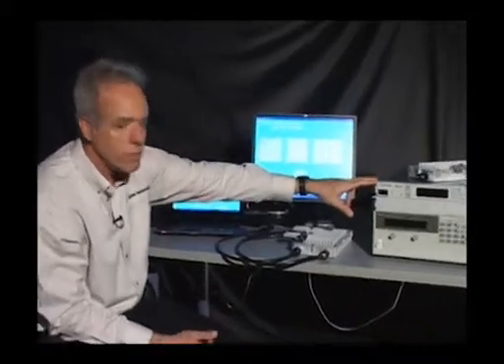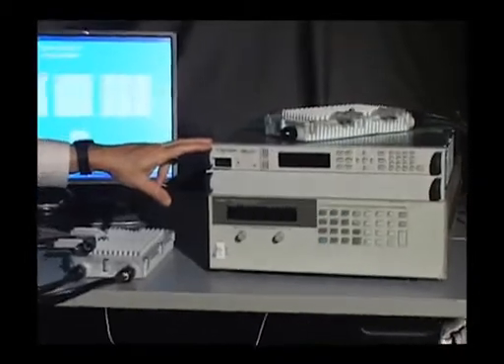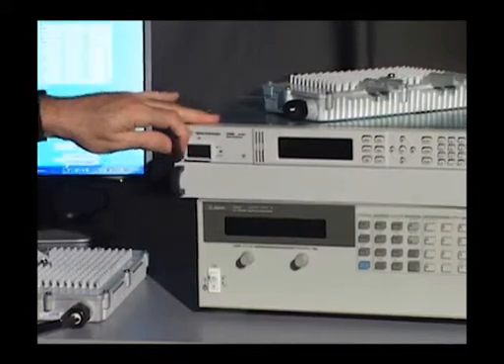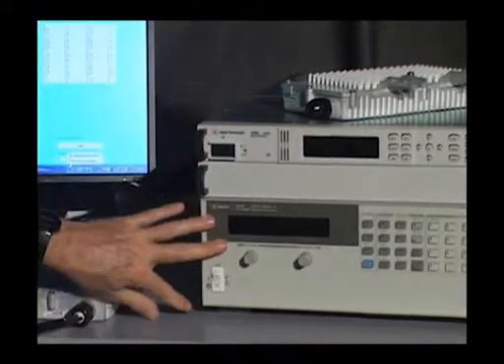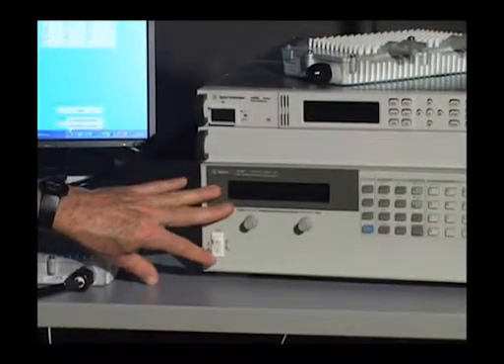We'll also take a look at some demonstration software that I have here and what we'll be doing is instead of using an actual solar panel that would provide power to the microinverter, Agilent has a solar array simulator which is this box here on the top and I also have an AC source that I'll be using as a grid simulator down here below.